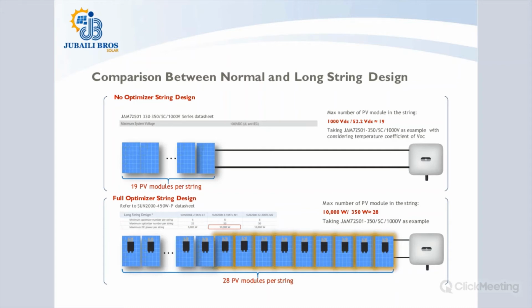Now, because we use the full optimizer system, and you saw how the optimizer installation is done, the PV modules yield their power parameters to that of the optimizer. So for that reason, when we are doing the calculation for the long string, and as I just mentioned in the previous slide, if it's a 3-phase system, the total maximum DC power per string is what? It is 10 kilowatts. So we simply divide this 10 kilowatts by the panel wattage, and we are getting 28 modules. Now, it will be amazing. The question will be, how are you able to do this? It is very simple. We will explain it in further slides that will come.